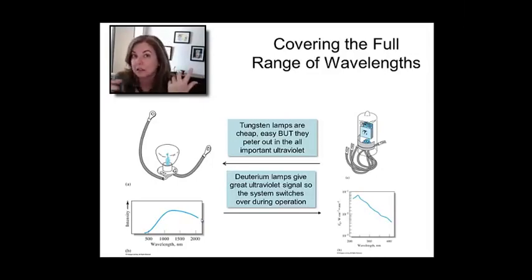Because, depending on the speed of the scan that you're doing, when you change a particular optic in your system, you can sometimes see a glitch. It's usually right around 400, maybe 450 nanometers. So often you do combine light sources so that you have plenty of light over the full range of the spectrum that you're interested in.